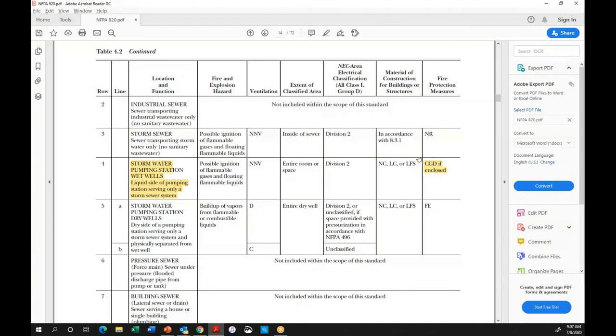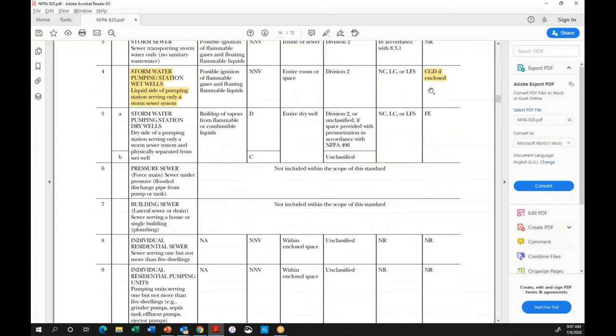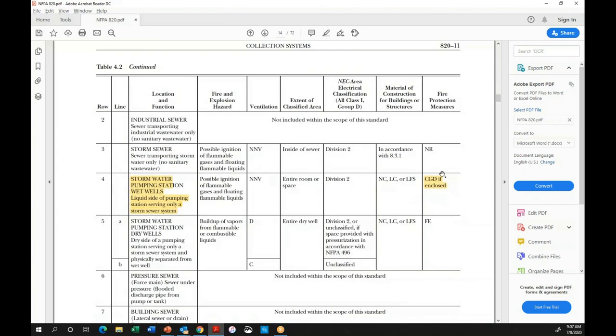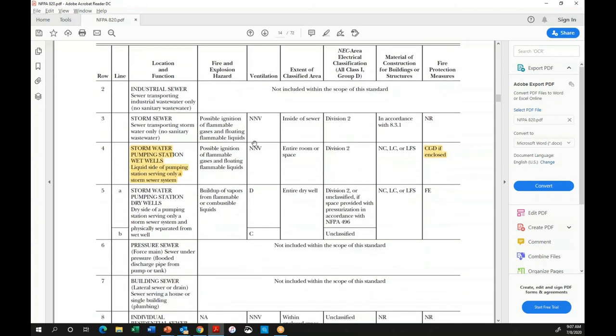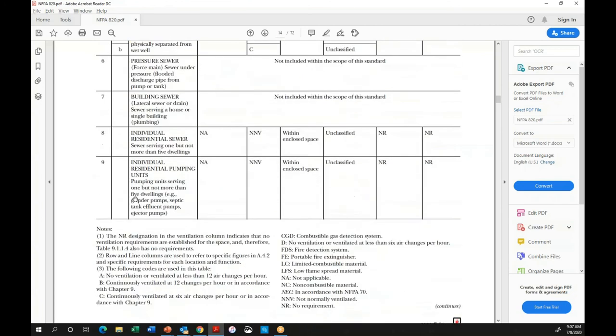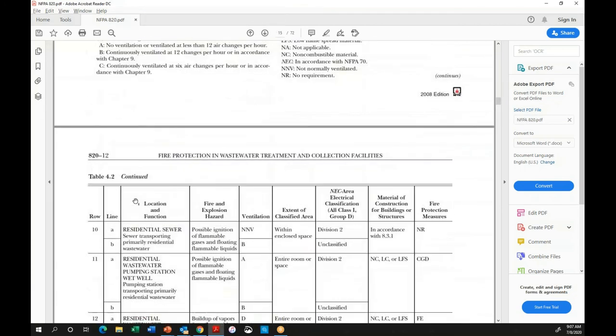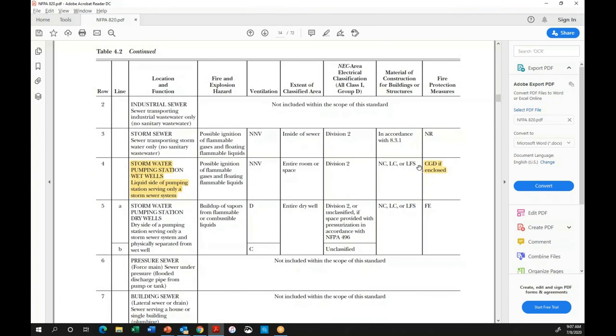You'll see here, this is the one we're focusing on, being a gas detection manufacturer, is the combustible gas detection if enclosed. So you'll see the CGD designation throughout here and some other areas, it'll say if enclosed or whatever the condition might be for the measures needed. The example I've shown here goes through many different examples, as you can see. So it covers just about every process within a plant or transmission line where you're going to have a collection of the sewage and different things. This one is the stormwater pumping station, wet wells.